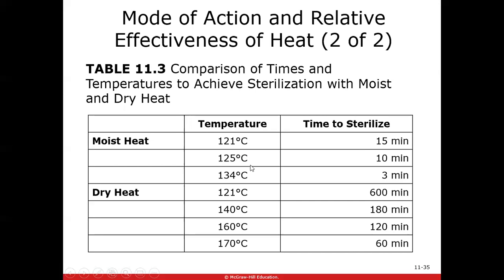If it was at 125 degrees Celsius, which is about 257 degrees Fahrenheit, it takes about 10 minutes. So the higher the temperature, the less time it takes. 134 degrees Celsius, which is 273 degrees Fahrenheit, would only take about 3 minutes. That gets really hot, and it would only take about 3 minutes to kill all the microorganisms. That's with moist heat.